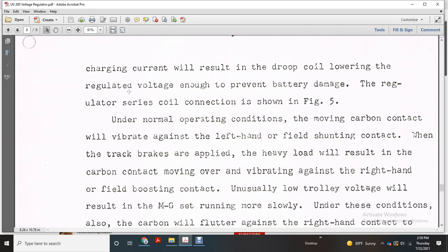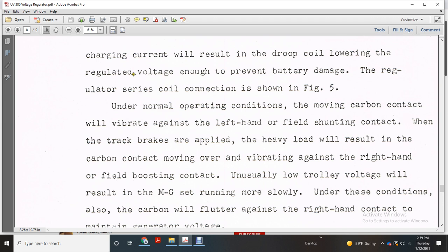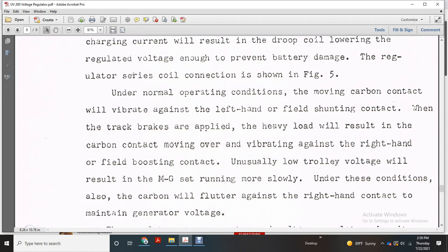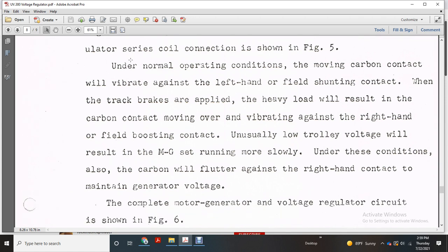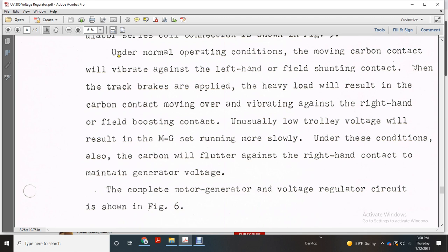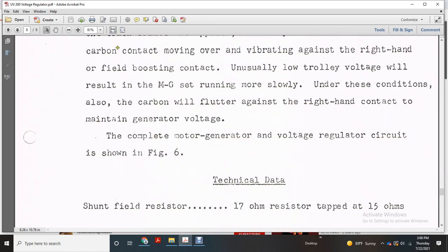Under normal operating condition, the moving carbon contact will vibrate against the left-hand field shunt contact. When the track brakes are applied, heavy load will result, with the carbon contact moving over and vibrating against the right-hand field boosting contact. Unusually low trolley voltage results in the MG set running more slowly. Under these conditions, the carbon will flutter against the right-hand contact to maintain the generator voltage. The complete motor generator voltage regulator circuit is shown in figure 6.